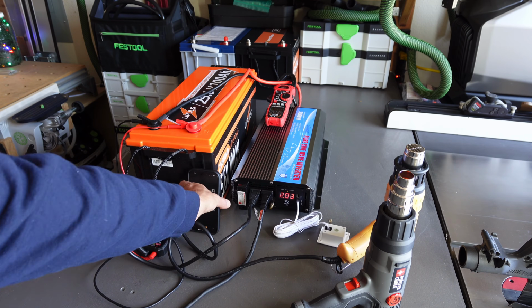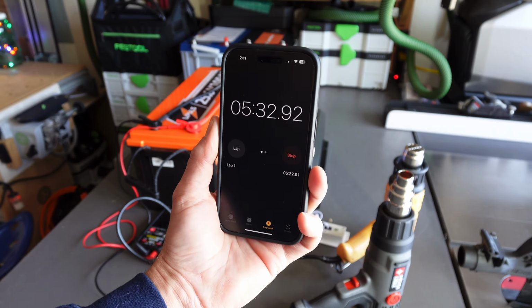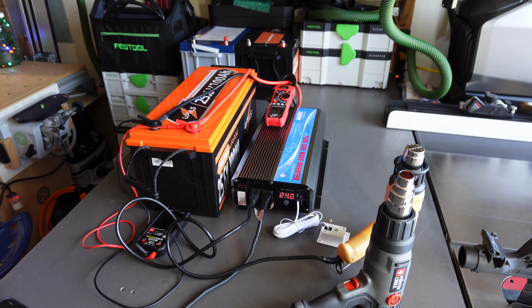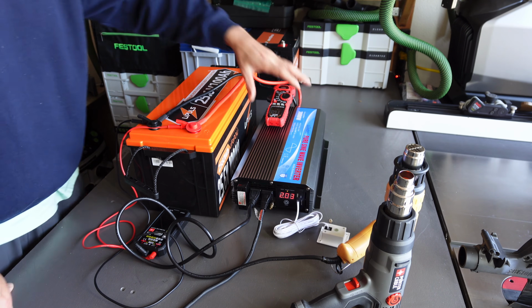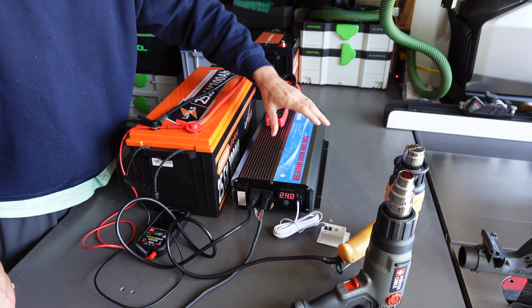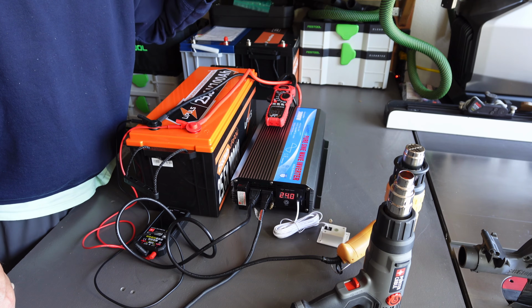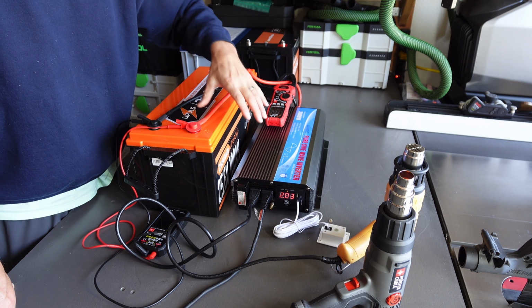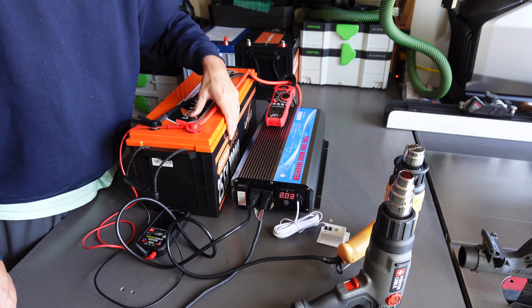All right, folks, well, we are at 5 minutes and 30 seconds into this test, pulling 94 amps, which by my calculations is around 2300 watts. And again, this inverter's a 3000 watt rated continuous inverter, but I don't want to try to get up to that because I don't want to trip this BMS and shut the battery off.